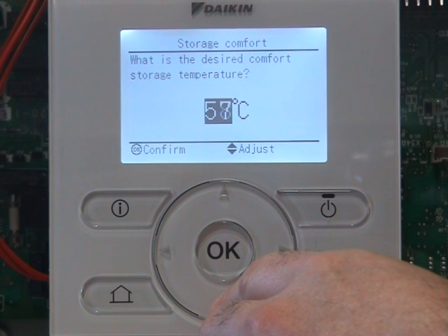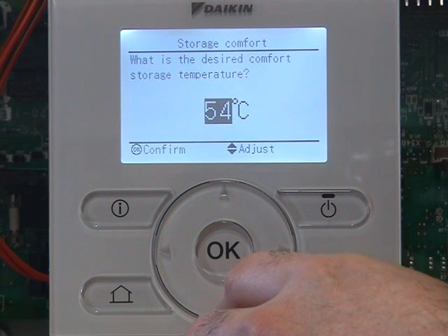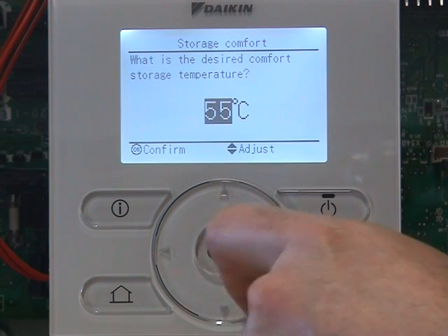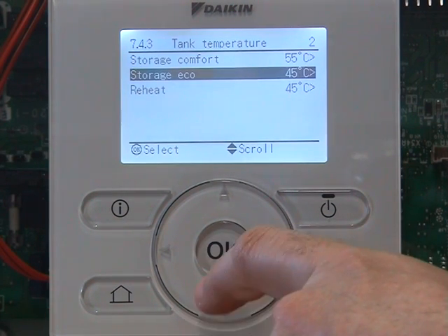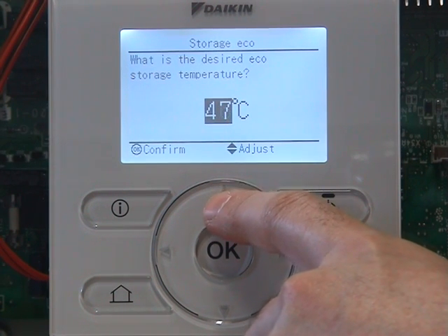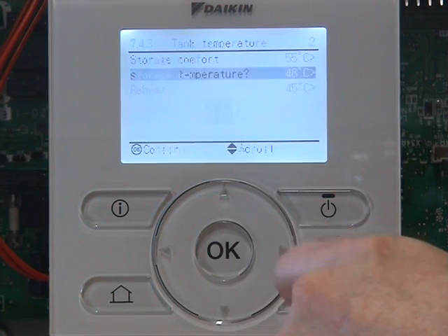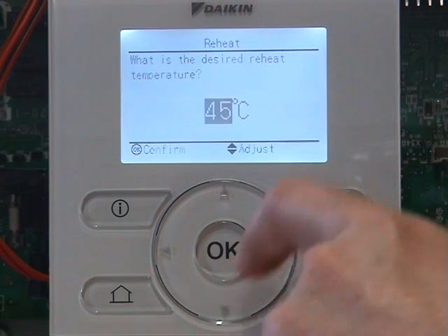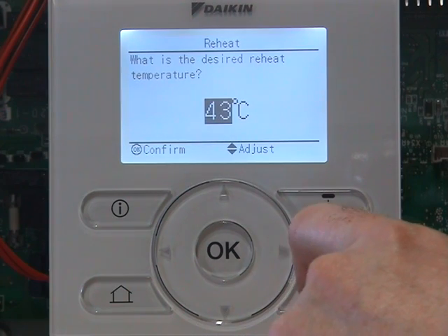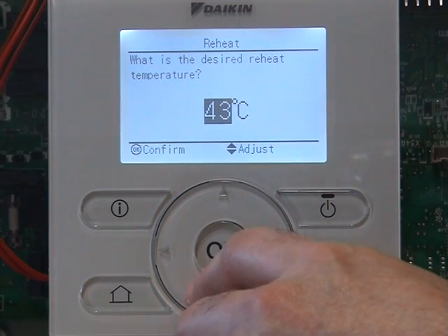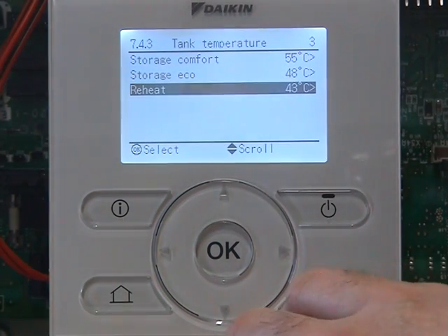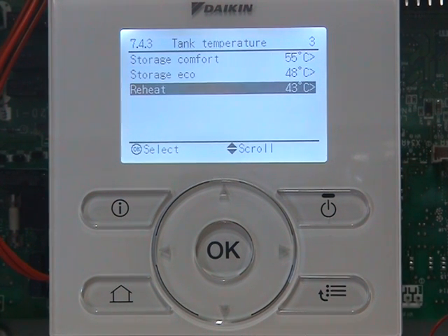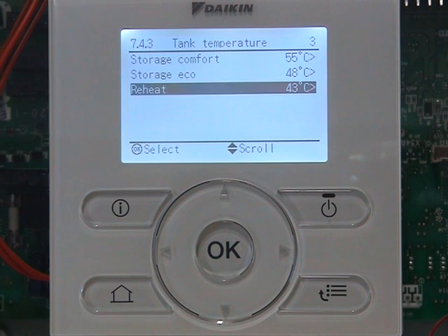For this job, we've got a medium amount of hot water required, so we'll set storage comfort at 55. Storage eco will be a lower set point temperature — we will set that at 48. Our constant reheat will be set at about 43. So the tank will never drop below 43 degrees. That means that when we do ask the system to heat the hot water, it's not having to heat from such a low value.